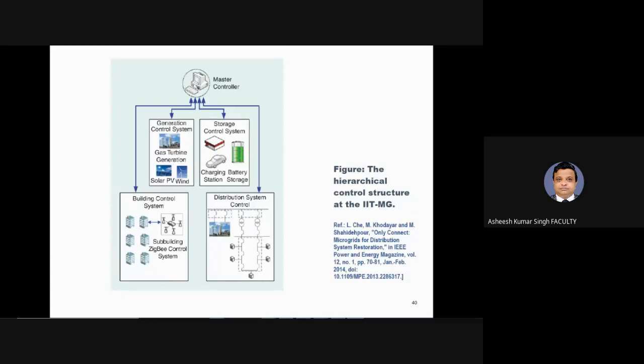One more thing I would like to express: this master controller is part of the hierarchical controller structure of this particular microgrid, and it obtains the campus generation and load data through supervisory control and data acquisition. Different arrangements are done for this, as this microgrid is equipped with building meters and 12 phasor measurement units (PMUs). These together report building electricity consumption and instantaneous voltage and current data of the DER units, with a sampling rate of 1 signal per cycle for the master controller.